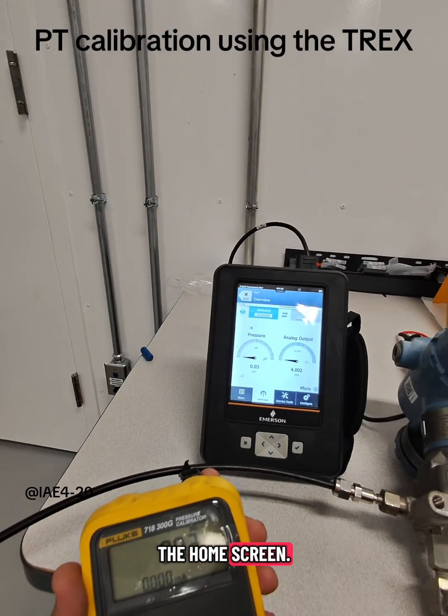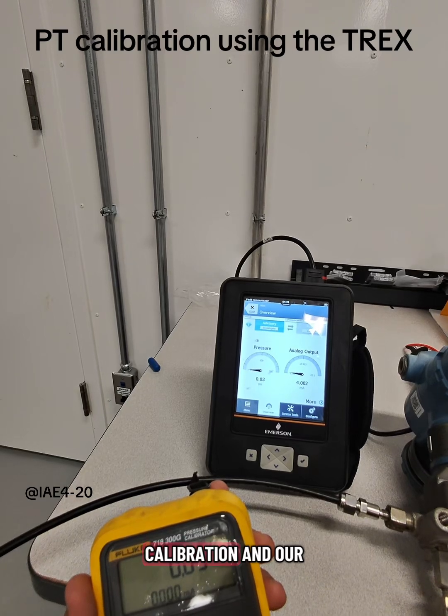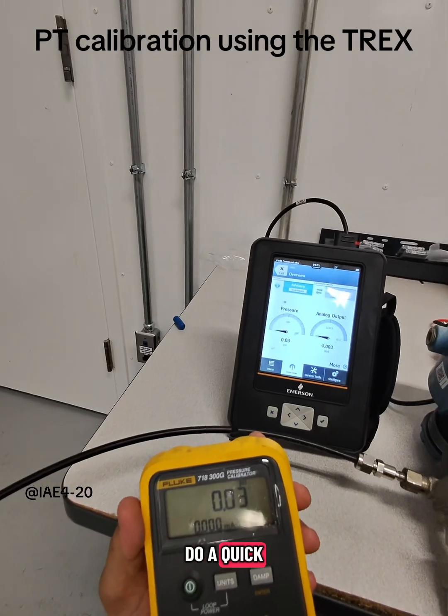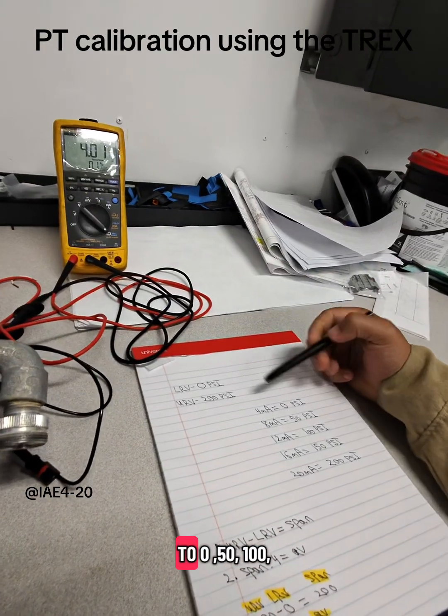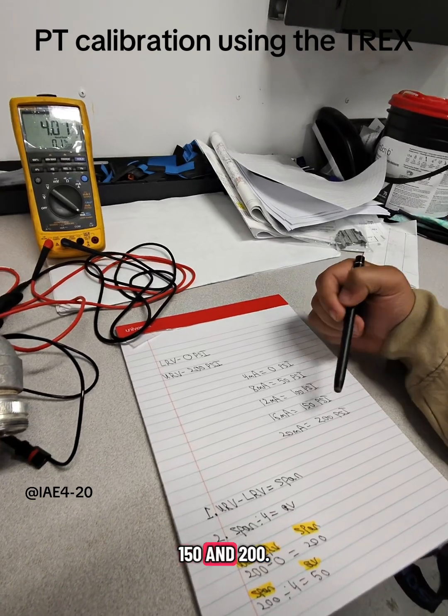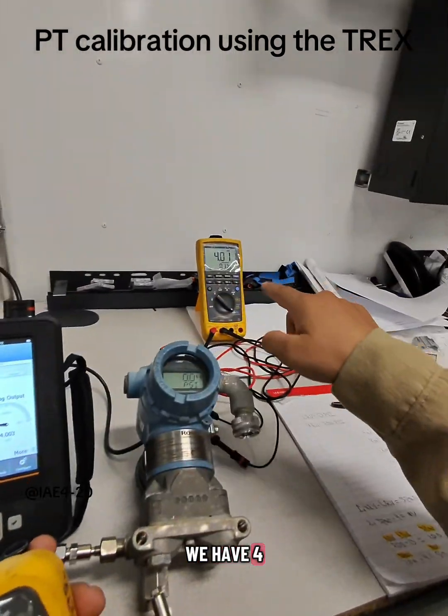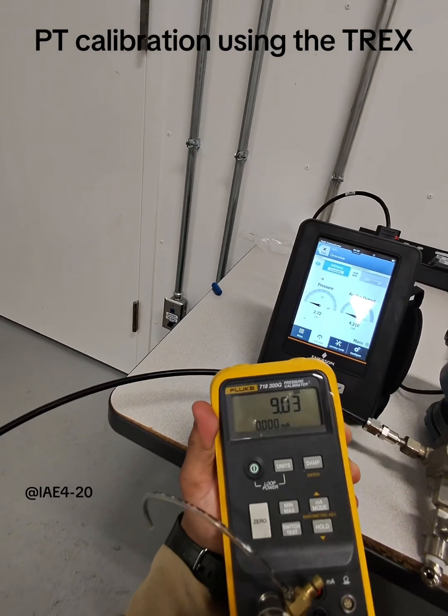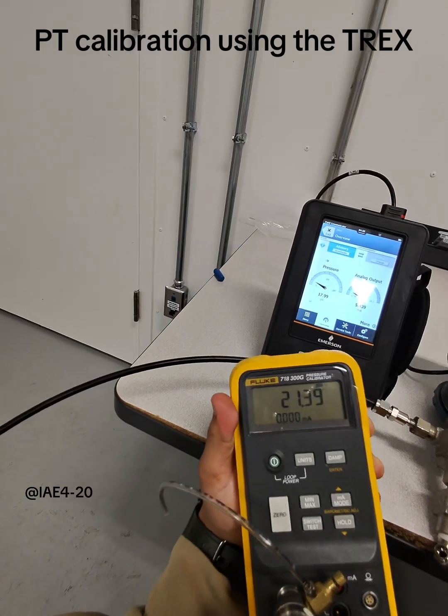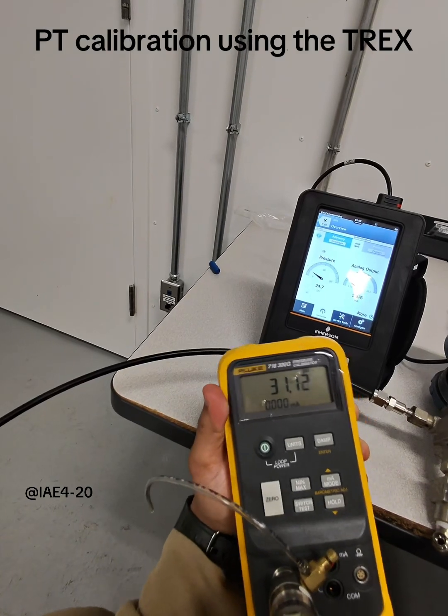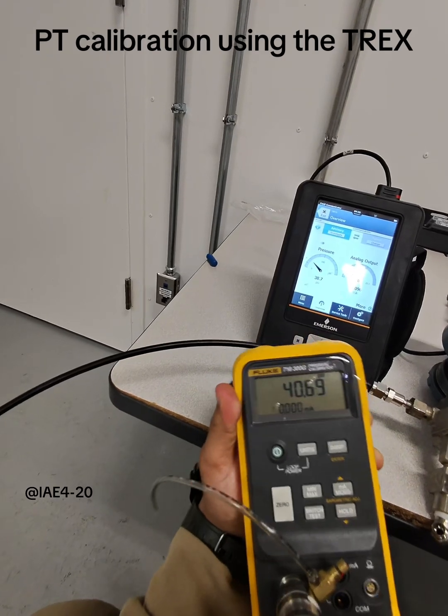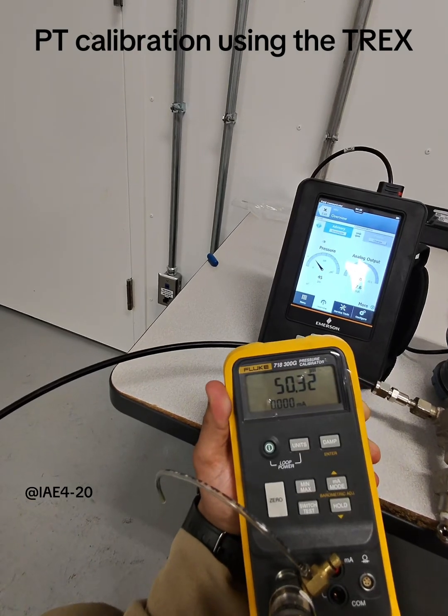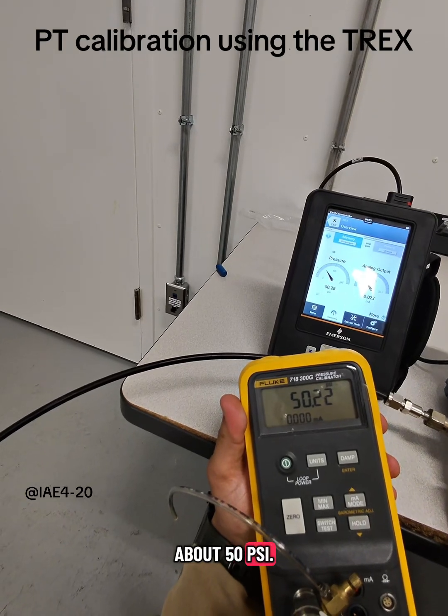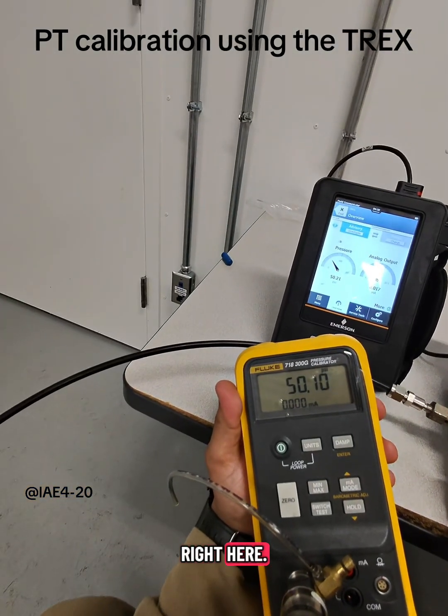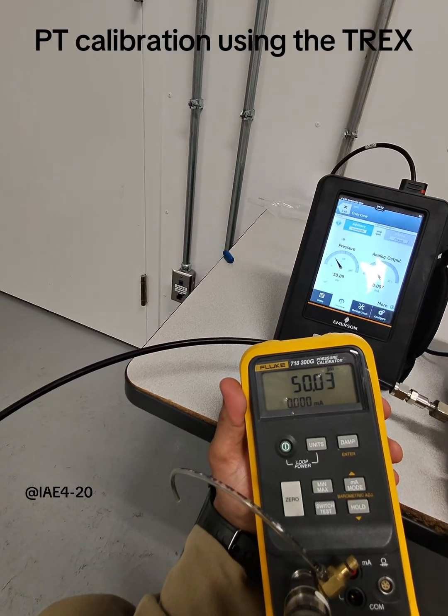Okay, so I'm back here at the home screen. At this point, we already did our low range calibration and our upper range calibration. So we're going to go ahead and do a quick 5-point check. So this is what we're going to take it to: 0, 50, 100, 150, and 200. So 0, obviously we have 4 milliamps. We're going to go ahead and take it to 50 psi, which is 25%, or 8 milliamps. We're at about 50 psi. Go ahead and do a fine-tune adjust right here. Alright, we're about right there.